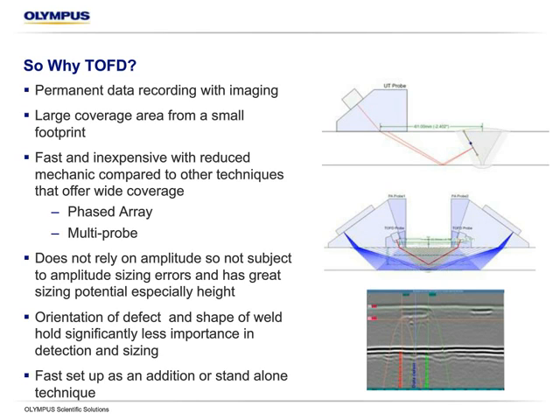It's also very fast and inexpensive. It's very fast because we're only using one beam. In contrast to phased array, for a typical 1/2 inch, 3/4, or 1 inch weld, we might have 70 different beams to get full coverage from both sides of the weld, whereas in that thickness zone, TOFD might be able to do it with some very small dead zones, but pretty much 100% coverage with just one beam. So that means we can move at a magnitude 70 times faster in a typical application than a phased array. It's also comparatively very inexpensive, usually very similar to conventional pulse echo transducers, composite materials being kind of the high end of them, but you're talking hundreds of dollars typically versus maybe thousands for a phased array sensor.